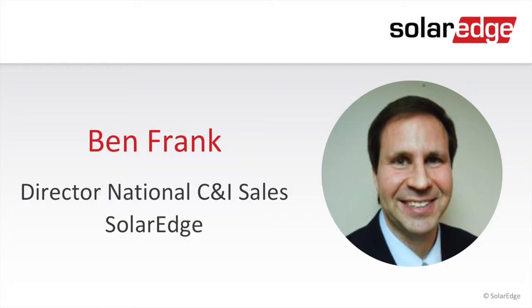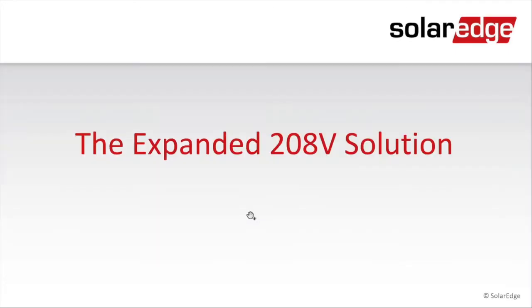So as Mike said, there's not a lot of native 208 string inverters on the market today. It's actually a pretty slim offering, and it's not like it was a number of years ago where central inverters were pretty prevalent in the market, and it was very easy to get even a 500 kilowatt central inverter at 208 volts. So today, for the most part, what you're looking at are 15 kilowatts or somewhere in that range or smaller. And as Mike said, it's really a 480 volt design that's been readjusted to give you a 208 volt output.